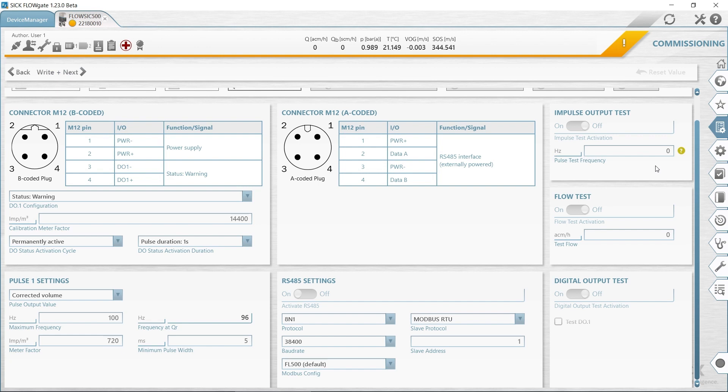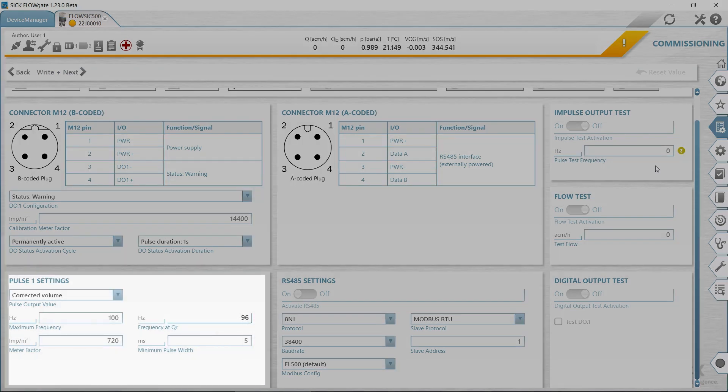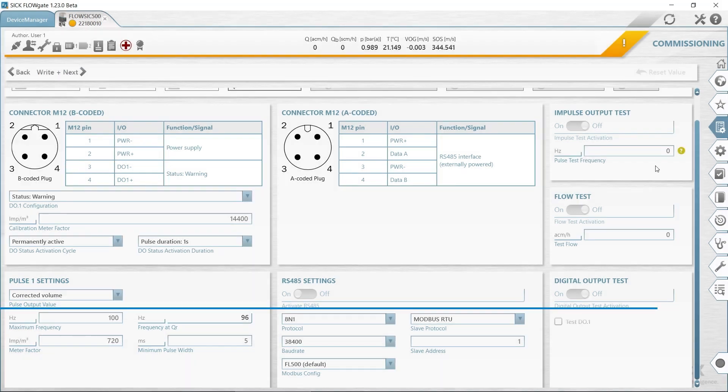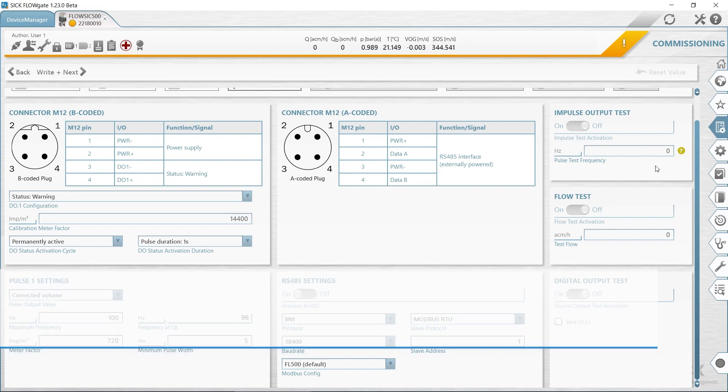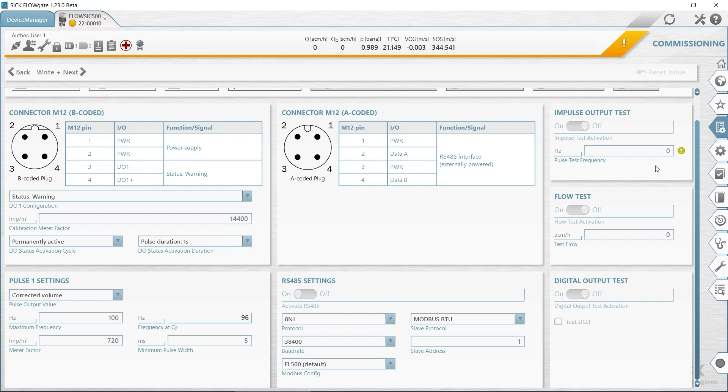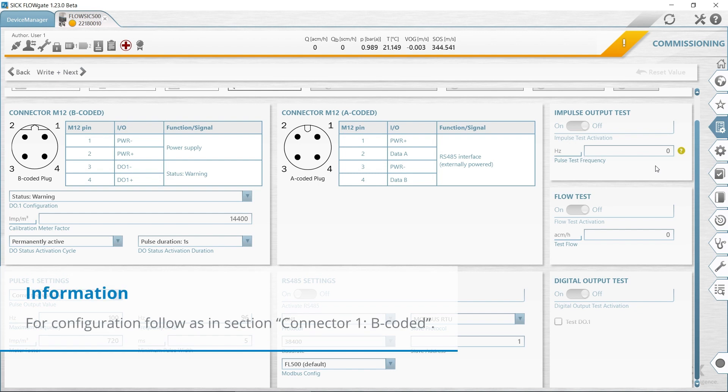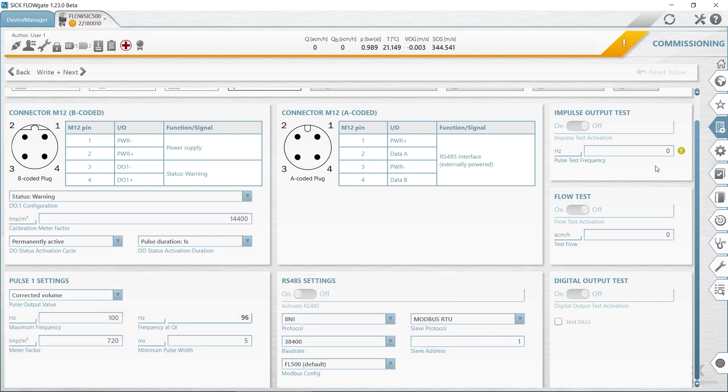The digital output of plug one B-coded can be configured as status or pulse output. Select the desired configuration. When configuring as a pulse output, enter the maximum frequency and the minimum pulse width in the pulse one area. When configuring as a pulse output, make sure that the overload frequency of 120% of Q max is covered and that the connected device understands the frequency. Depending on customer specifications, the A-coded plug 2 is configured as status pulse output or as a serial interface like RS485.